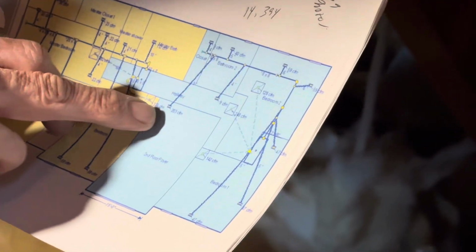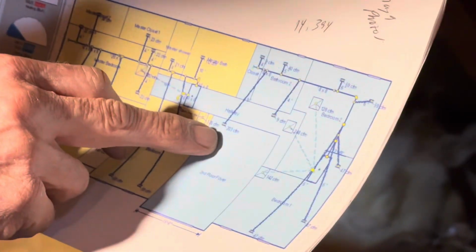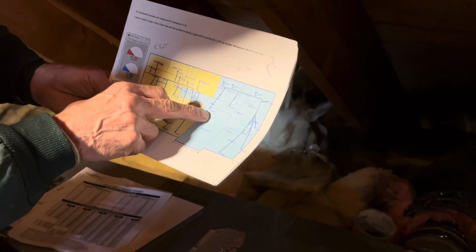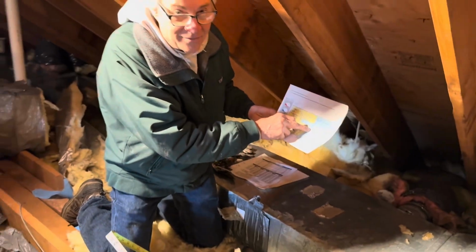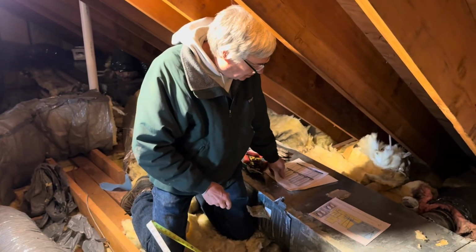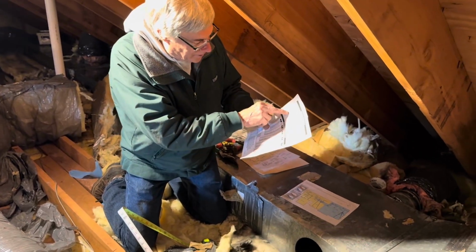And then there's another part which needs 203. So 164 and 203 would be 367 cubic feet a minute of air. So 367, we go back to our original of what we have, and we have 480. So we have an adequate supply of air.